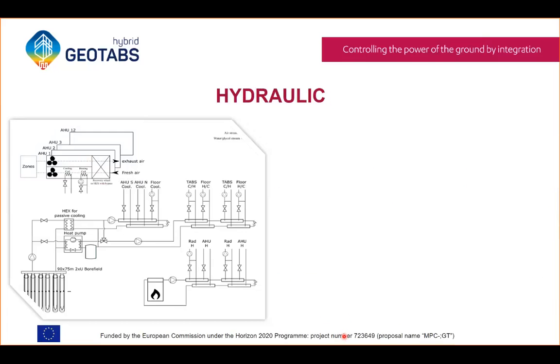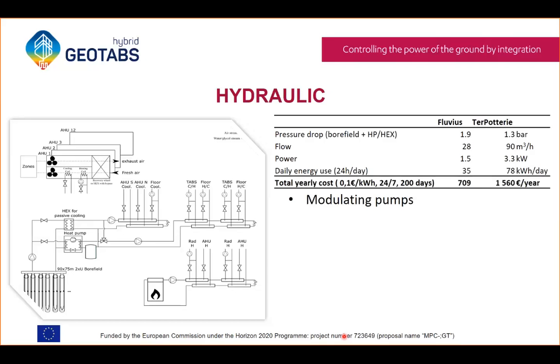There are also a few points to take into account for the hydraulics. Let me start with pumps, because for a hybrid GEOTABS system, the pump power may be significant. Again, taking some numbers from Fluvius and TerPotterie, we had a pressure drop of between, let's say, 1 and 2 bars in the bore field plus the heat pump and the passive heat exchanger, and we had a significant flow rate in this. So if we consider a pump running at full power 24 hours per day, because it's not modulating and not cleverly controlled, and this for 200 days a year, because it's used for both heating and cooling, then we would end up with rather high numbers, such as 700 to 1,500 euros per year.